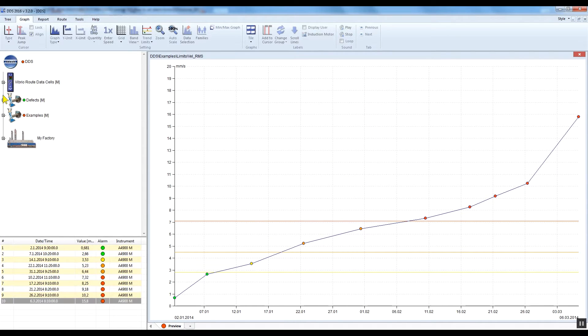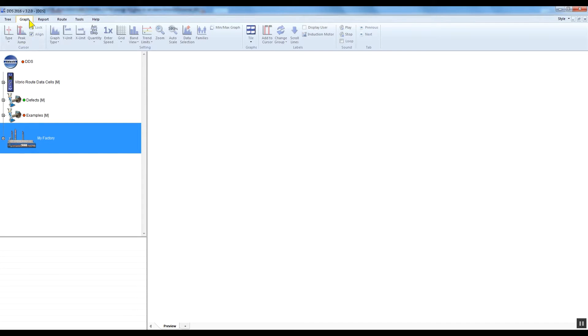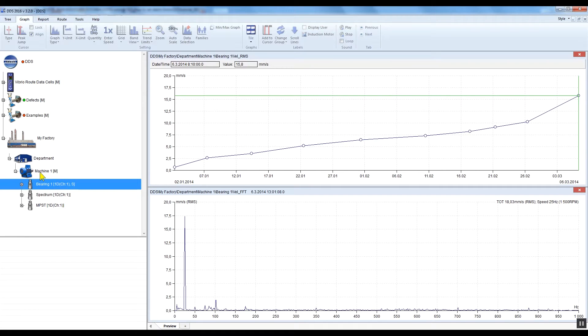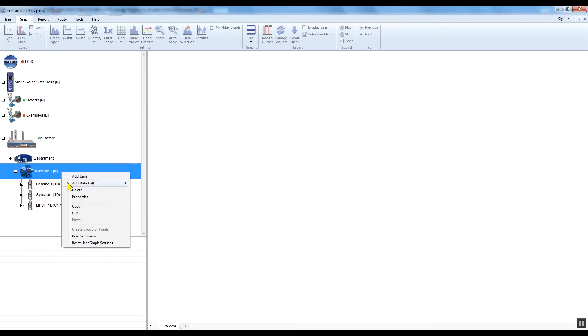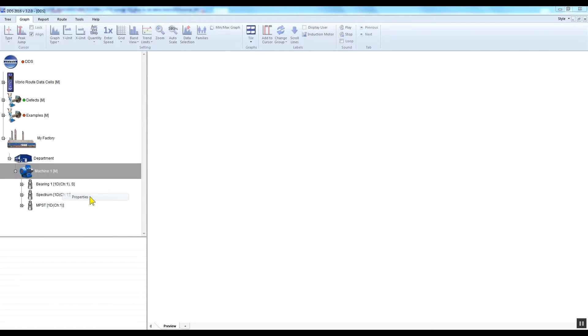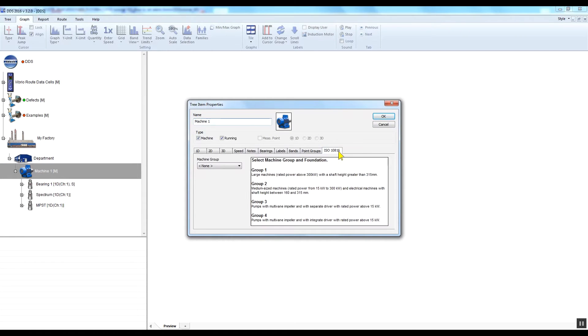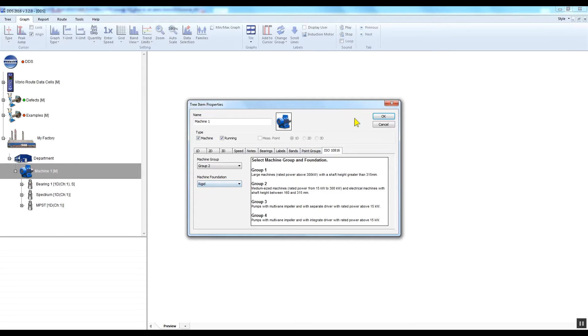Let's start with the first: alarms according to ISO 10.816 standards. We will work on the graph tab where we can see the data preview. First of all, you have to define the ISO machine group to your machines — you cannot do that on the measuring point nor on the data cell. Right-click on the required machine and select Properties. Go to the ISO 10.816 tab and select the required machine group and its foundation. Groups 1 to 4 are described in the right window. See the Vibrio manual for more information about ISO 10.816 standards and their limit values. Confirm by clicking OK.